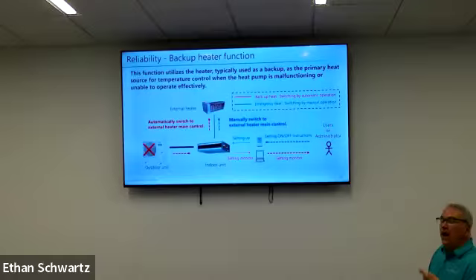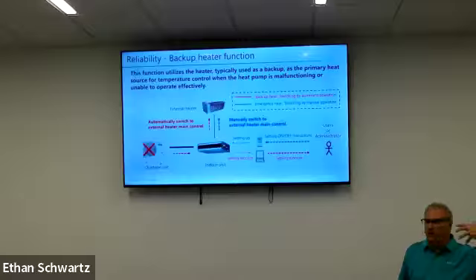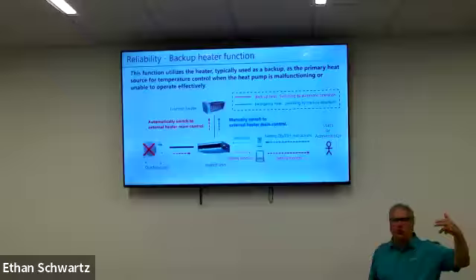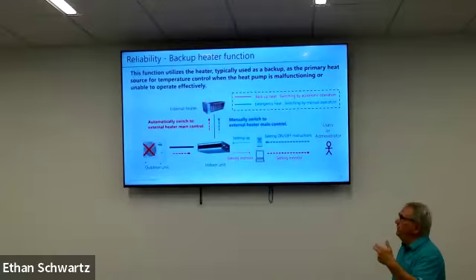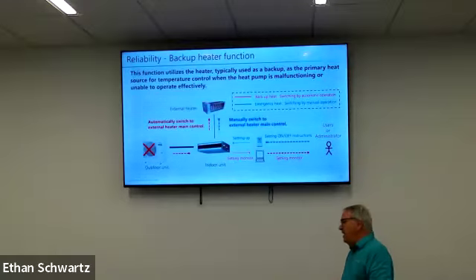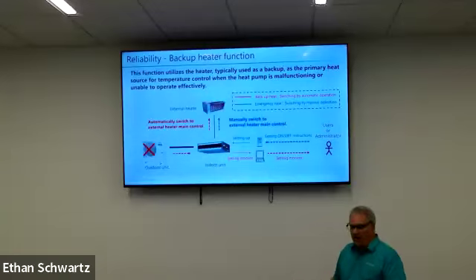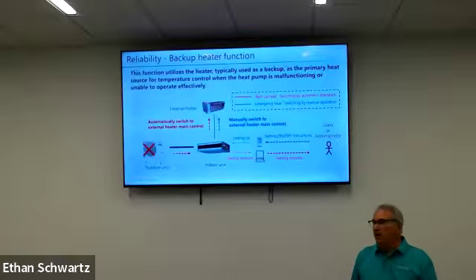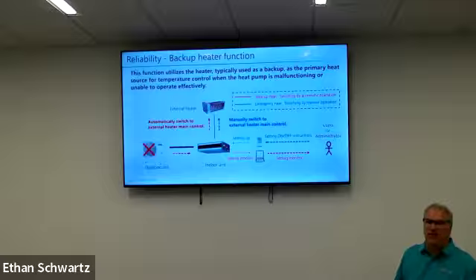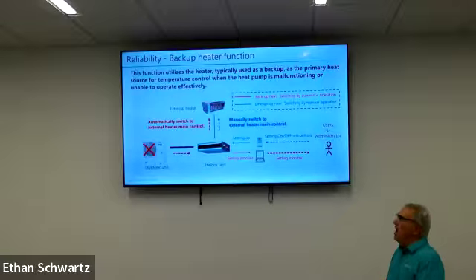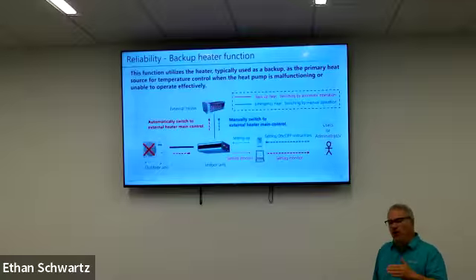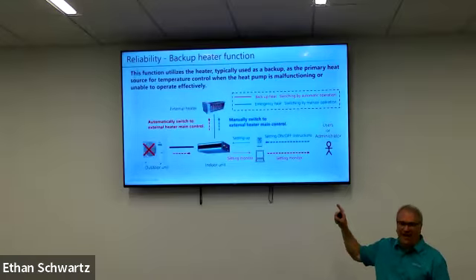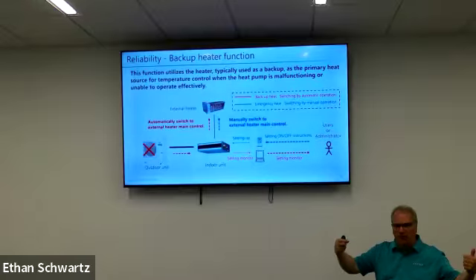Now, about what I mentioned regarding the 4 circuit breaker spaces and the two feeding the indoor unit: if I had a VRF indoor unit and a 208 volt single phase power supply, and I hooked up to it and put our control on, I could make it run sitting here in this room. They will run independently. Unlike on the H series, where even with our 1-to-1 ducted systems, if you had an error, most likely that would shut down the indoor unit. On VRF, it does not, because they have separate power supplies.